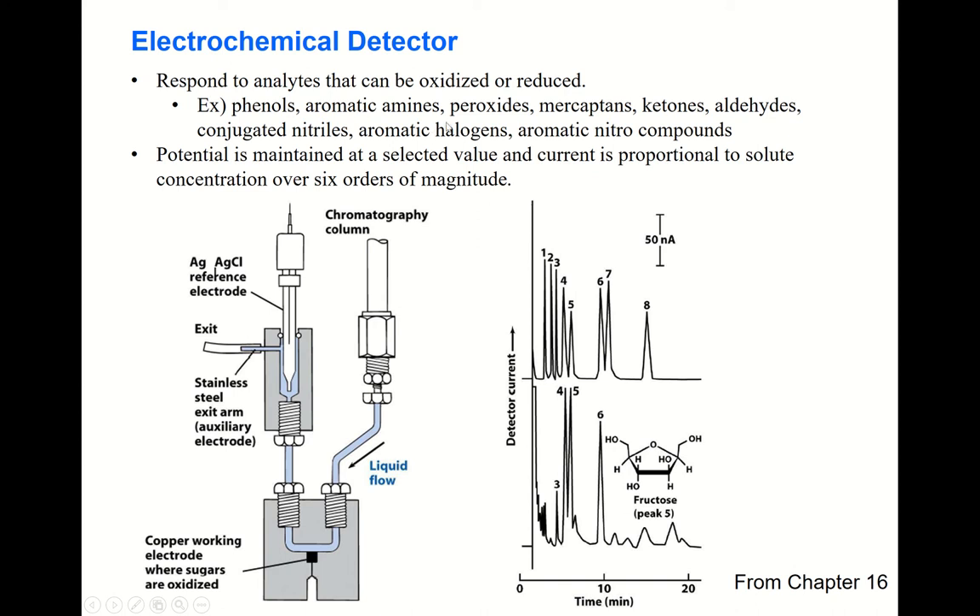This detection method is not universal — its application is rather confined to organic molecules such as phenols, aromatic amines, peroxides, mercaptans, ketones, aldehydes, conjugated nitriles, aromatic halogens, and aromatic nitro compounds, because these organic molecules can be oxidized or reduced electrochemically. A constant potential is applied, and the current is proportional to solute concentration over six orders of magnitude — a big advantage of electrochemical detection.